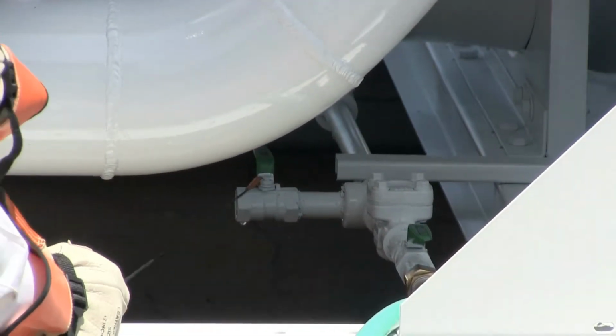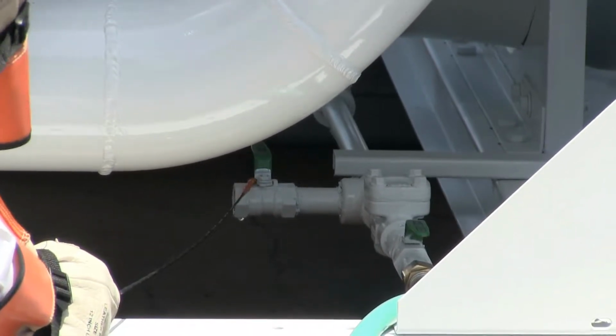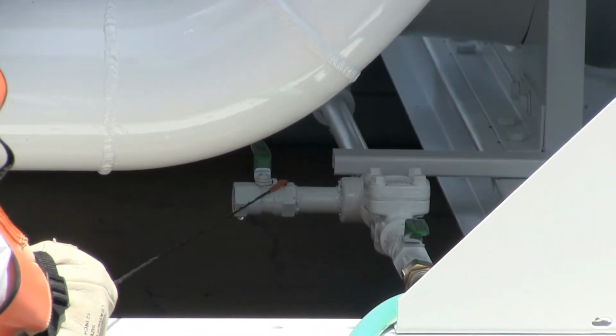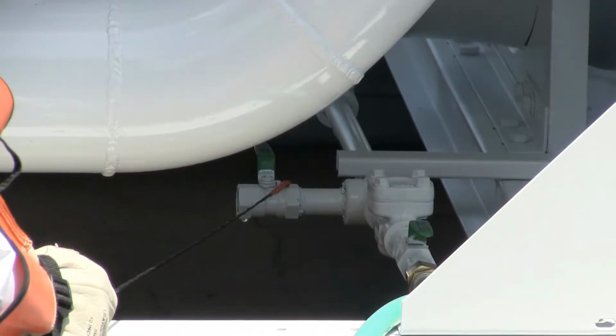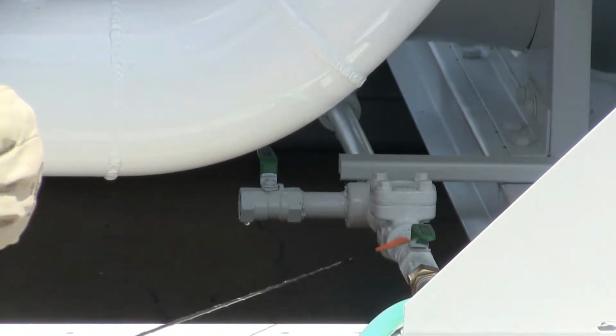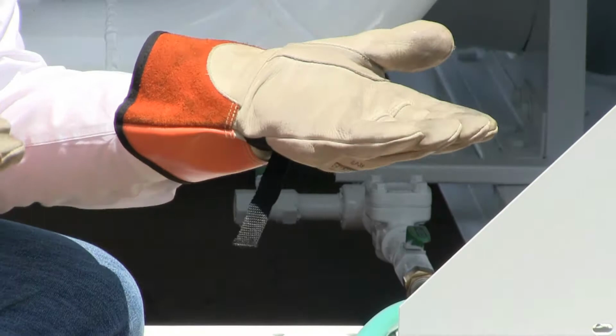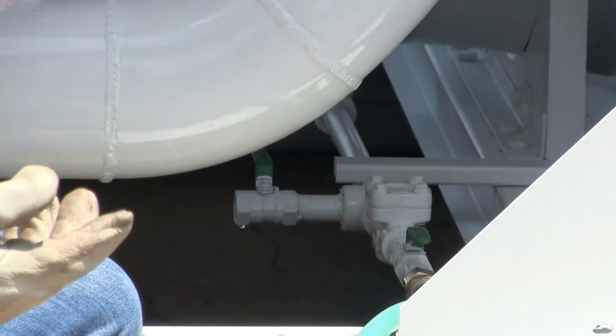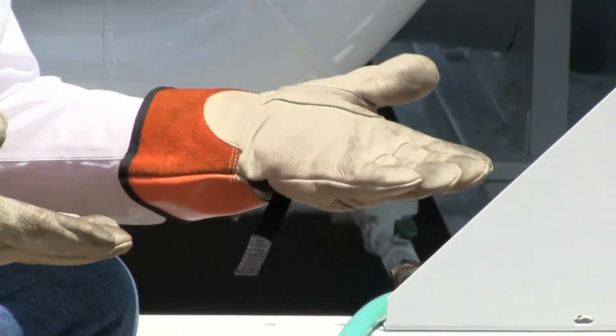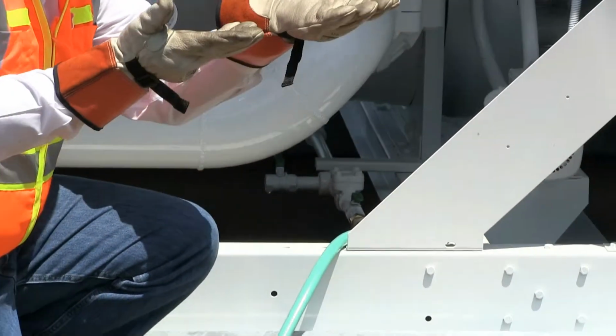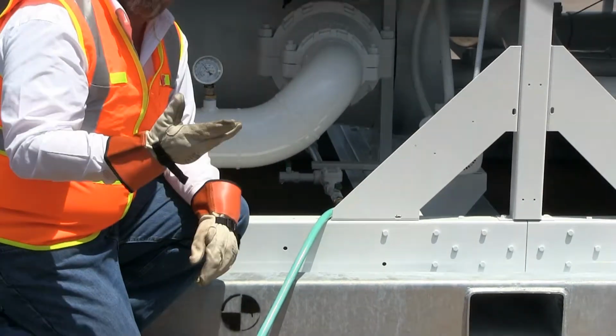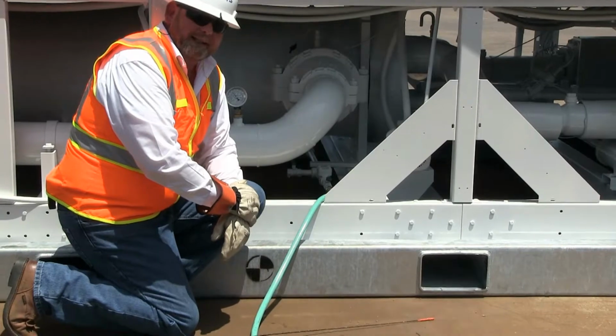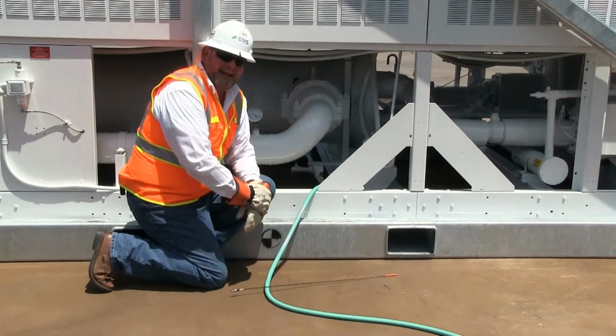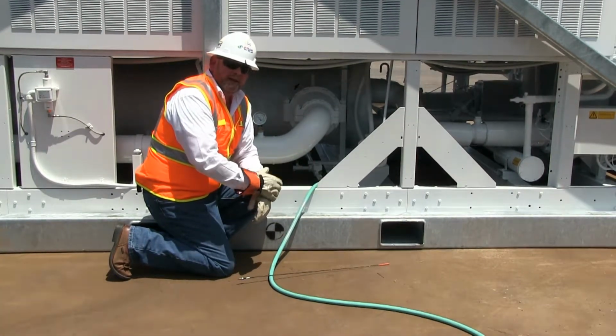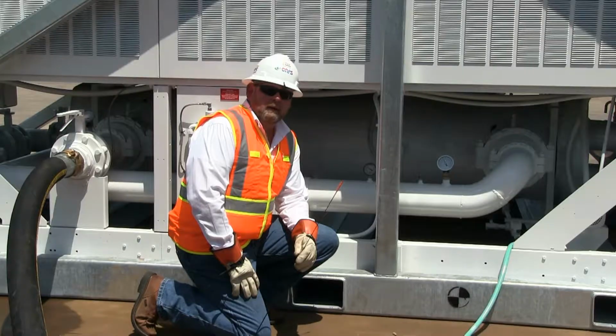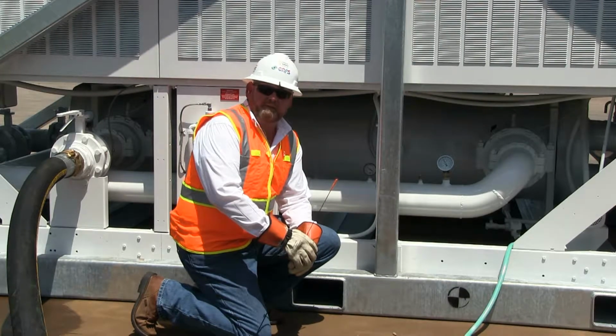This is the drain valve over here. We'll be using that when we take the chiller and remove it off the site. We'll use that as our low point drain. But as we fill the system up, we're filling from the bottom of the barrel with the vent line open. There's a high point vent that's open, and we're filling from the bottom to push the water up and push the air out. That's the whole point of filling from the bottom of the barrel, to get the air out of the system. You can't have any air in the system when you have a chiller because you can't have any heat transfer.